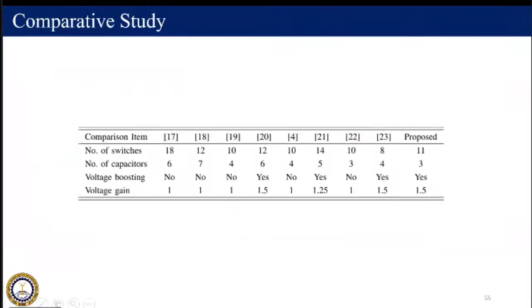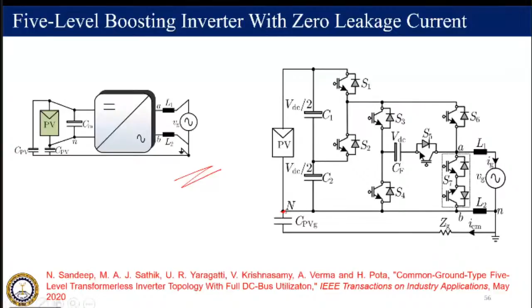Then we have the last topic, the common mode voltage reduction with zero leakage current. Here you can see the topology proposed: we had a direct connection of the neutral with the grid neutral, that is, the negative point with the grid neutral. These are the operating modes.